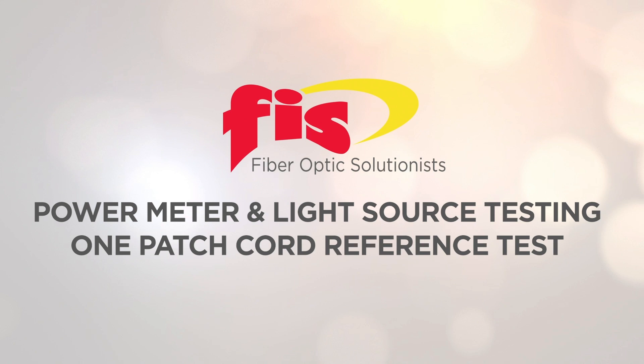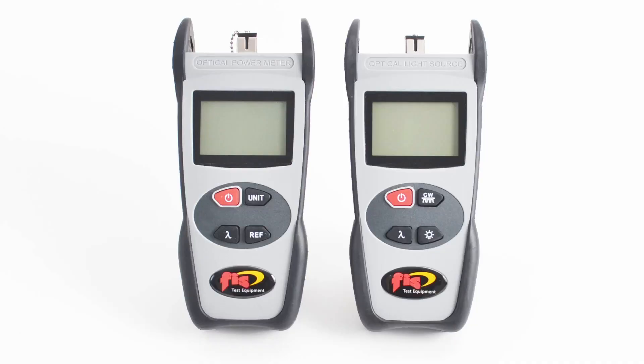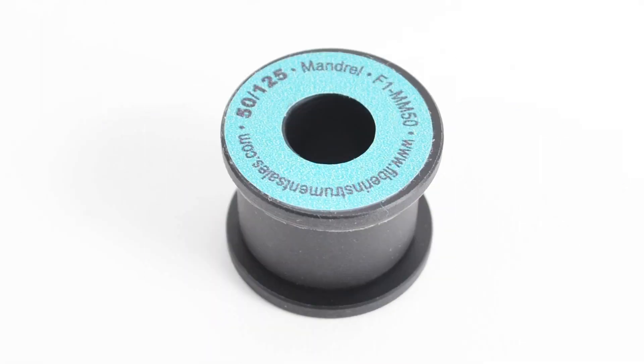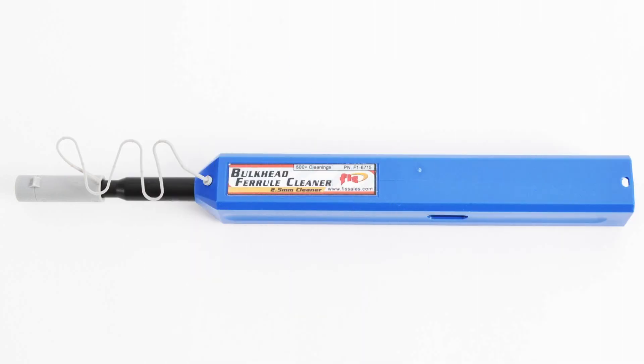Here are the items necessary for testing: FIS Power Meter and Light Source, patch cords and an adapter, mandrel for multi-mode, and an FIS One-Click Bulkhead Ferrule Cleaner.